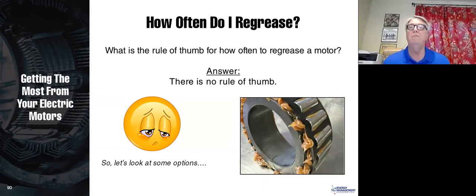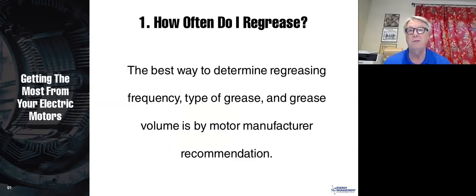Now, this can be the last thing I talk about. What is the rule of thumb for how often to re-grease a motor? And the answer is there's no rule of thumb. It depends on some factors. So what I'm going to do is take you through 5 ways of determining this, and you can pick which one you want to use. So number 1, this might seem like a cop-out, but it is not. This is very important. If you have a motor data sheet that tells you how often to re-grease that motor, that's the best information you're going to get. So that is the best way to do it.